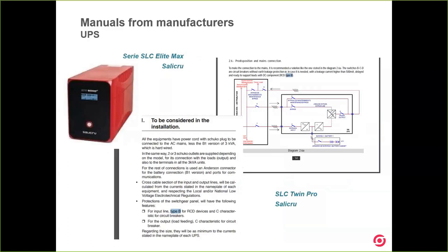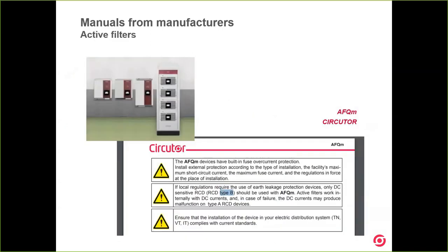Continuing with the same manual in the warnings section, again it says we need to use an RCD type B. Let's follow with more examples. Manuals from Salicru, a UPS manufacturer, for two different models — SLC Elite Max and SLC Twin Pro — both manuals state the UPS should be protected with type B RCDs. Next: active filters from Circutor. As manufacturers of the solution, we know it must be protected with RCD type B, and it's included in the manual. For EV charge, depending on the power, type A or type B solutions should be used.